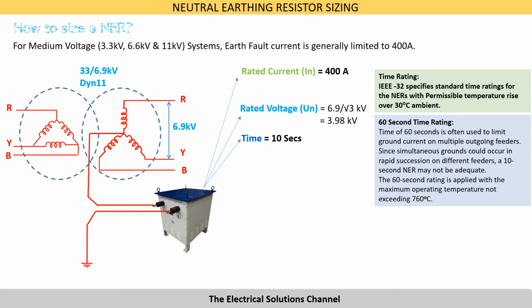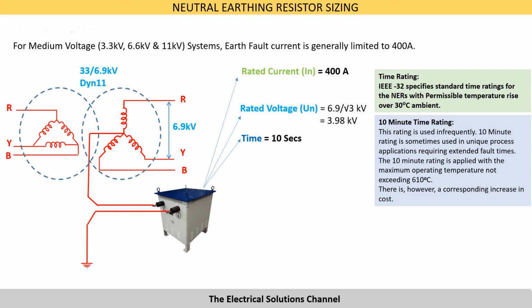A time rating of 60 seconds is used for NERs when we need to limit ground fault currents on multiple outgoing feeders. Since simultaneous ground faults could occur in rapid succession on different feeders, a 10-second NER may not be adequate. The 60-second rating is applied with the maximum operating temperature not exceeding 760 degrees C. A 10-minute rated NER is used infrequently. The 10-minute rating is sometimes used in unique process applications requiring extended fault times. The 10-minute rating is applied with the maximum operating temperature not exceeding 610 degrees C. There is, however, a corresponding increase in the cost of the NER.